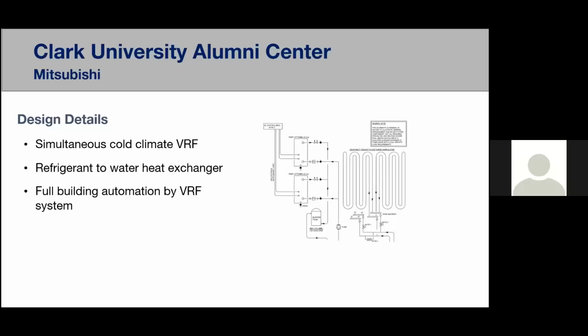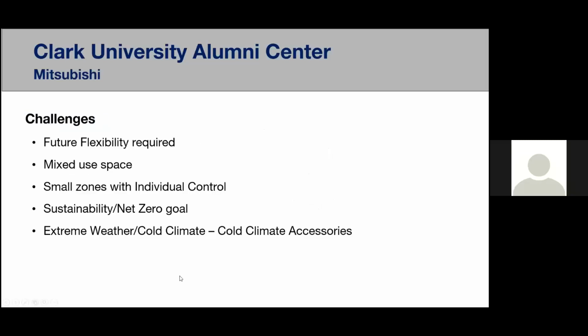But one thing that we had to use was a full building automation system with VRF to achieve certain functions, especially the energy efficiency that we needed in the space to get to the net zero point. So one of the challenges was future flexibility required. This was an alumni center, and they said, we want a lot of zones right now, individual zones, but 5 years from now, we might want to change it up. So maybe we want to take down a couple walls and make it into a larger conference room if that's what we need. So what we're able to do is micro zone the systems.